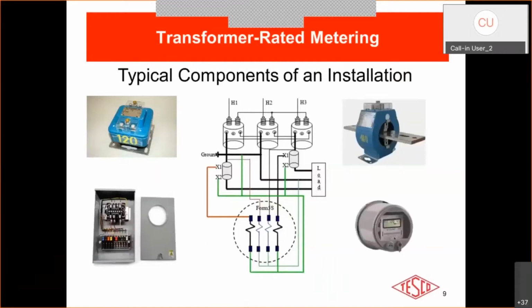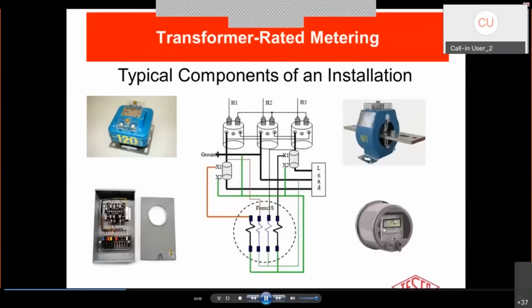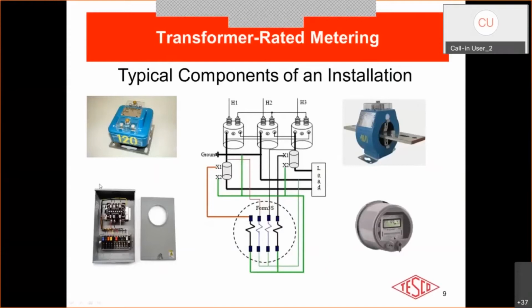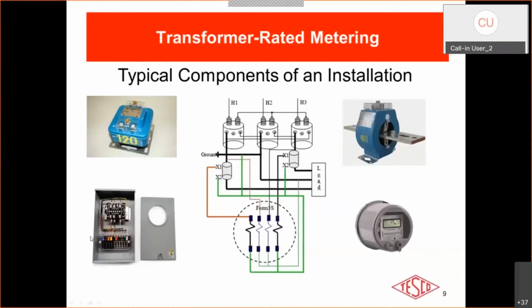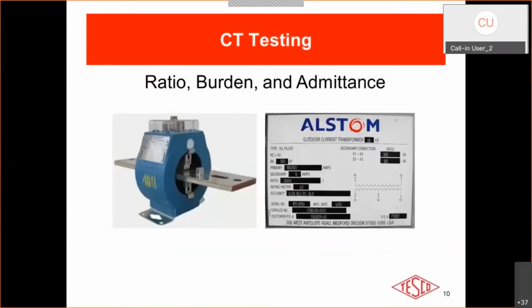Typical components of a transformer rated metering installation include your PTs, the CTs, the meter, a pre-wired meter enclosure, and in most cases, a safety test switch. Now we will discuss burden, ratio, and admittance testing in further detail.